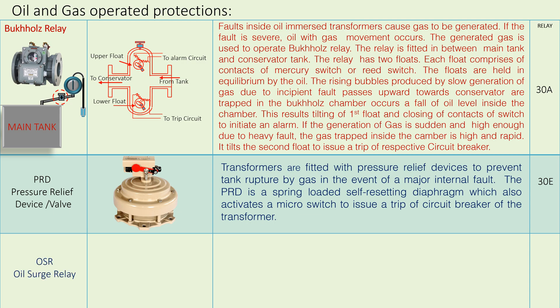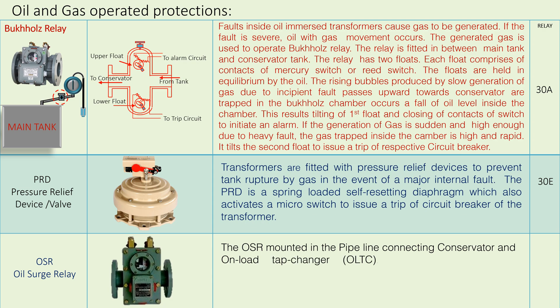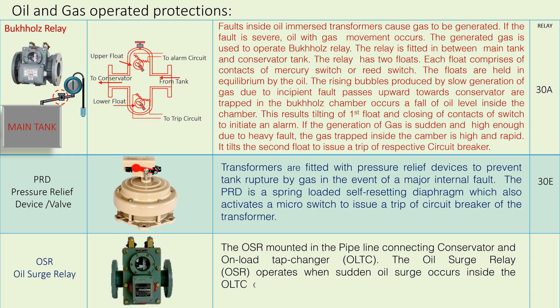OSR — Oil Surge Relay: The OSR is mounted in the pipeline connecting the conservator and the on-load tap changer (OLTC). The oil surge relay operates when a sudden oil surge occurs inside the OLTC, on the principle of the Buchholz relay, and initiates a trip without any alarm.